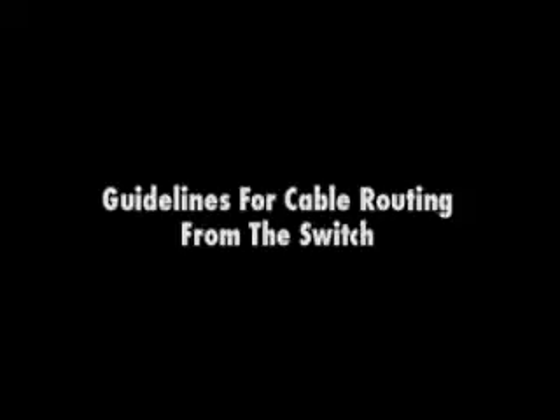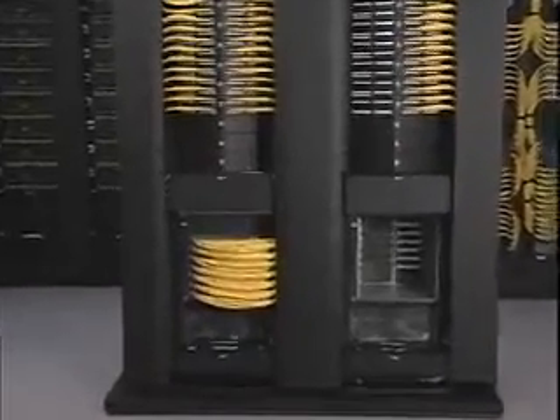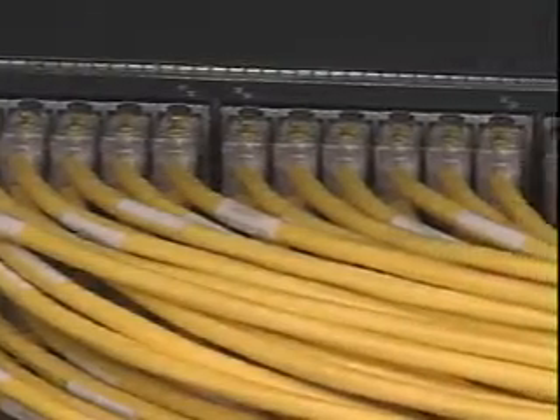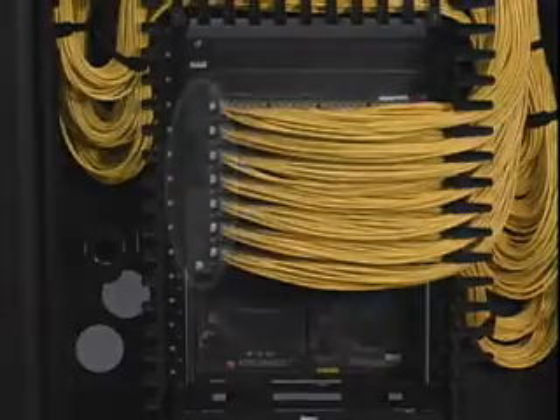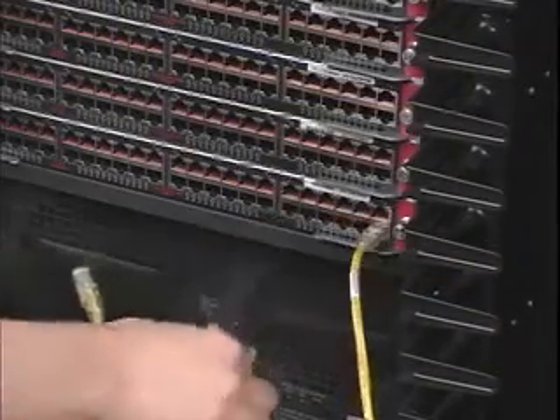Guidelines for cable routing from the switch are as follows. Method 1 requires that all patch cords be routed to the right in one direction. This will keep the fan blade clear of cables and allow it to be easily replaced if the need should arise. To begin populating the switch, start with the lowest card, or blade.